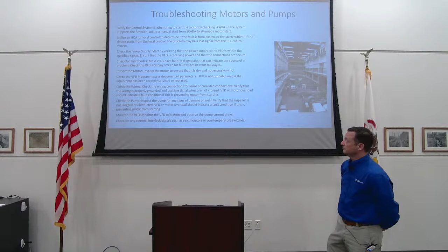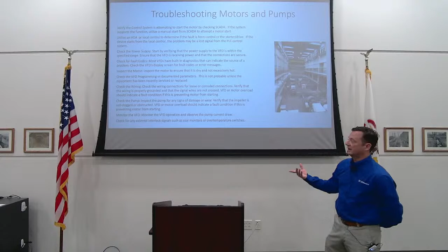Make sure that, obviously, the impeller is not clogged or obstructed, and that's something that operations people are usually going to be much better at identifying than the integrators. And then check for any external interlock signals. A lot of times, especially submersible pumps will have seal fail relays or over temperature relays on them. See if there's any ancillary devices that are going to trip your motor or pump out, and hopefully they have some sort of indication on them. And if you get to that point and your motor's tripping, VFD's not showing fault, you're probably swapping your motor out, right?